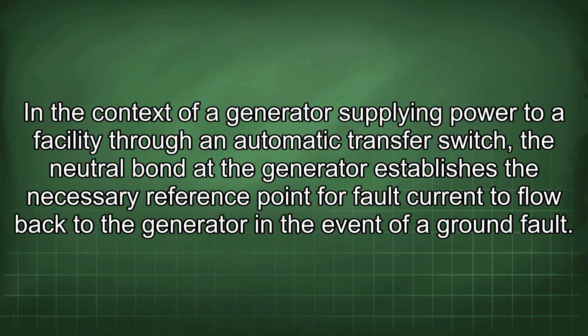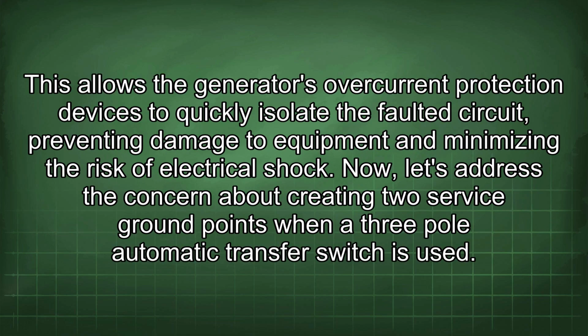In the context of a generator supplying power to a facility through an automatic transfer switch, the neutral bond at the generator establishes the necessary reference point for fault current to flow back to the generator in the event of a ground fault. This allows the generator's overcurrent protection devices to quickly isolate the faulted circuit, preventing damage to equipment and minimizing the risk of electrical shock.